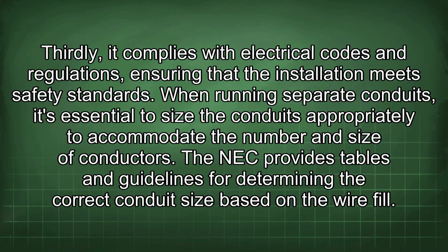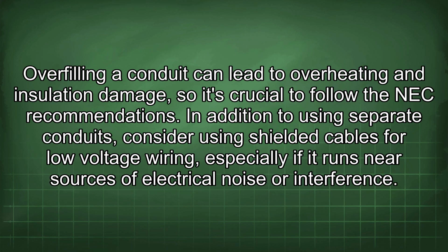When running separate conduits, it's essential to size the conduits appropriately to accommodate the number and size of conductors. The NEC provides tables and guidelines for determining the correct conduit size based on the wire fill. Overfilling a conduit can lead to overheating and insulation damage, so it's crucial to follow the NEC recommendations.